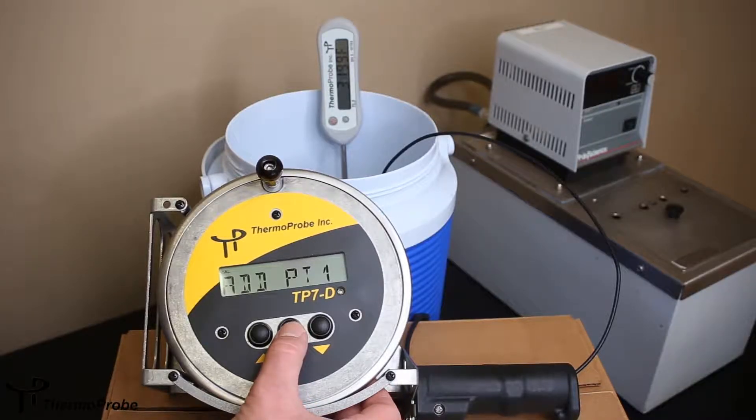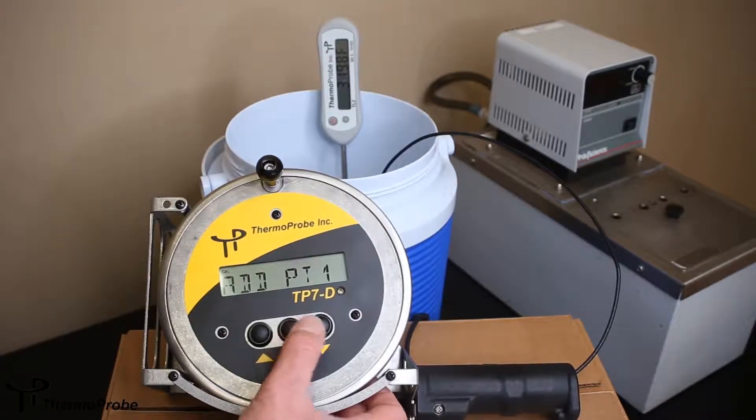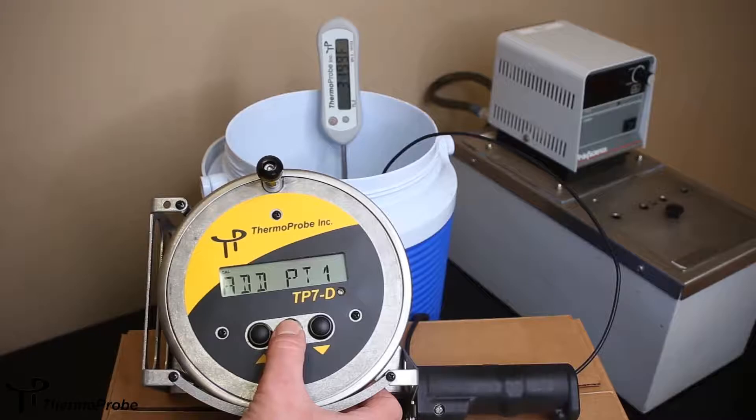To add the first point, it's recommended that you do the points in incremental order. You want to do a freezing point, and then your higher temperature second. So, I'm doing a freezing point, so I'll add point one.